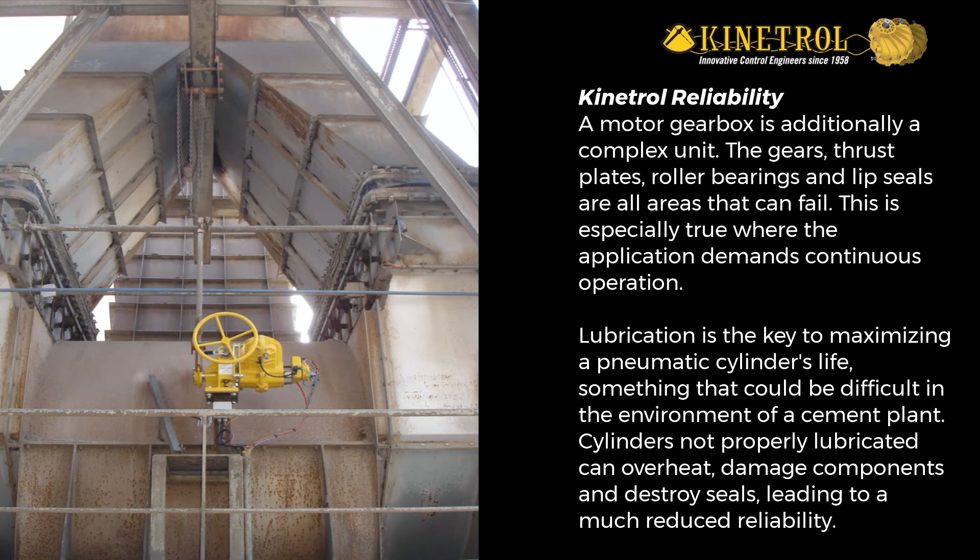Lubrication is the key to maximizing a pneumatic cylinder's life, something that could be difficult in the environment of a cement plant. Cylinders not properly lubricated can overheat, damage components, and destroy seals, leading to much reduced reliability.